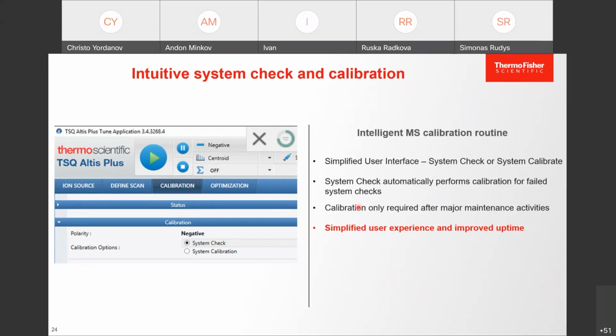System check can be scheduled according to your preferred time. So if everything is fine with the instrument, it can be done in the morning or in the evening when the instrument is not in a rush. And if the system check fails, only then does it go through system calibration, which takes a longer time. So basically you don't need to calibrate the system often, and system calibration usually is done just after annual maintenance activities or other bigger problems. Routinely, you are running just system checks, and automatically the system knows that if the system check fails at some point, then it needs to run system calibration, which improves uptime of the instrument.